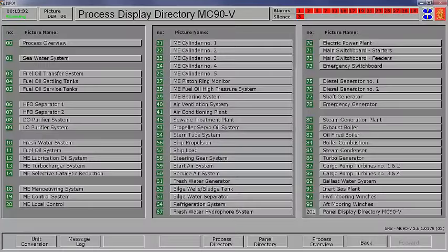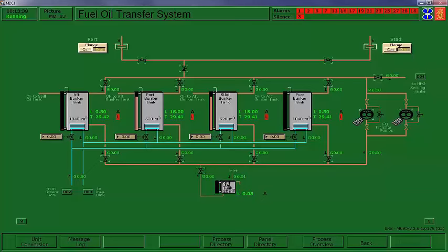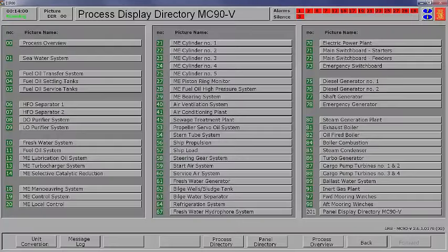So as that boiler starts producing steam, it's going to start going out there and do its heating. So we've got these two bunker tanks that we need to heat up. We're going to open up the supply to them at 100% right now. They're only at about 30 degrees C, so we cannot pump oil. This is too cold to even pump it. We could not transfer pump oil right now, so we need to start heating that. Then we'll work our way down.